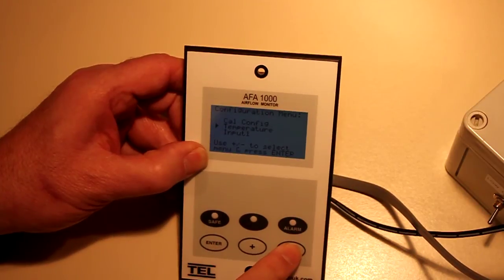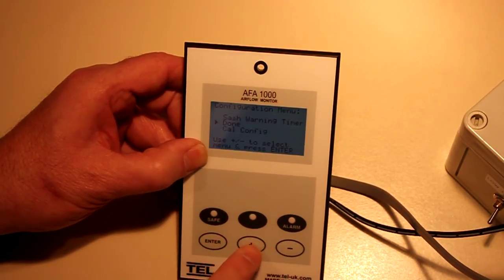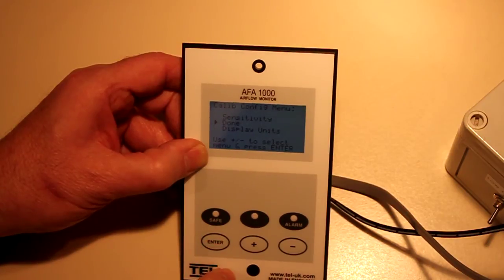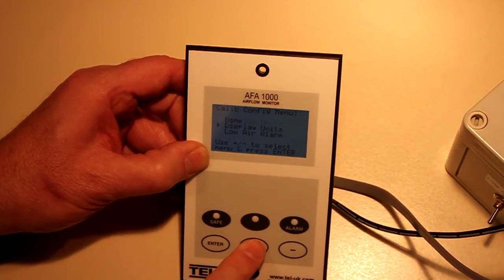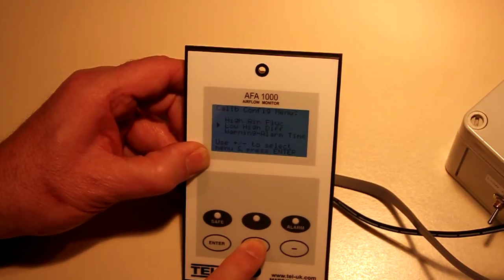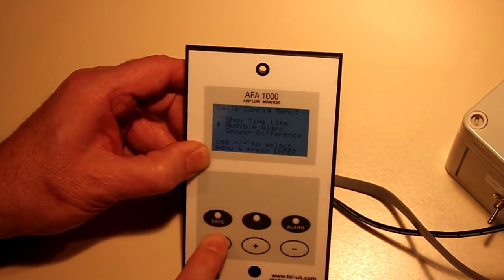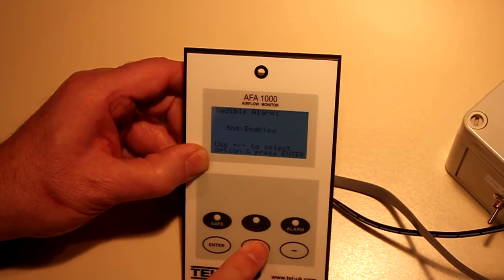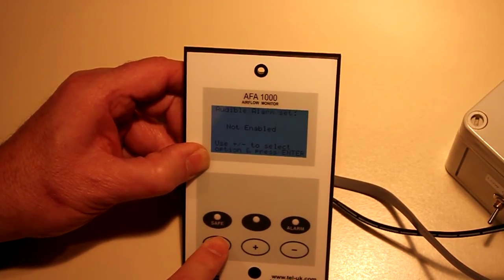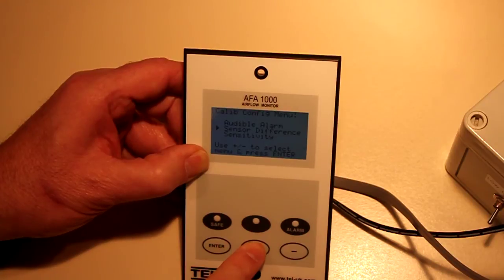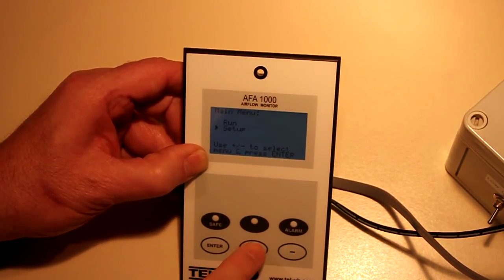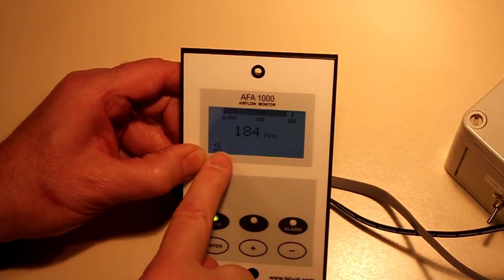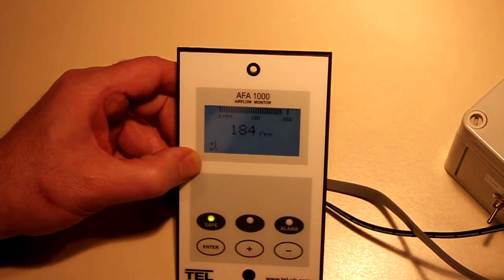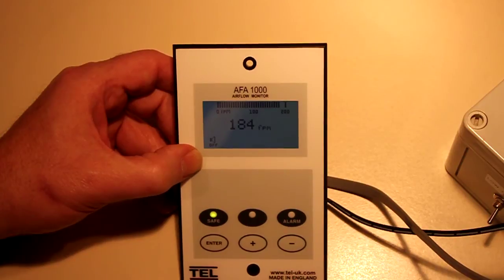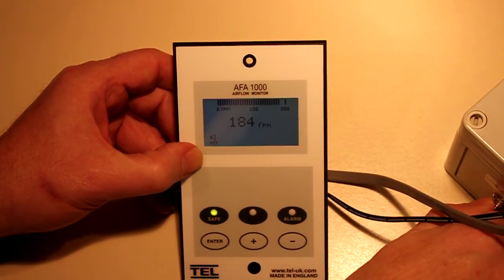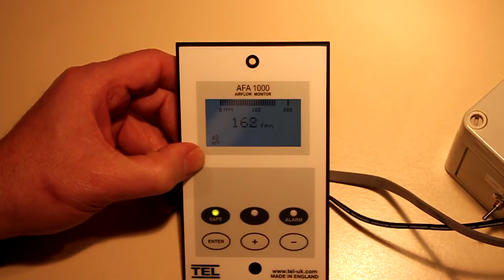To permanently silence the alarm, access the CalConfig menu, scroll to the audible alarm option, and toggle to Not Enabled. After returning to Run mode, the monitor display will show an icon of a horn with a line through it. In normal mode, the unit's green safe light will blink. When there is an air fail condition, the red alarm light will flash and the display will flash air fail, alternating with the velocity.